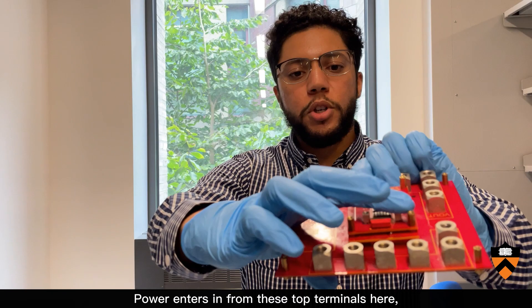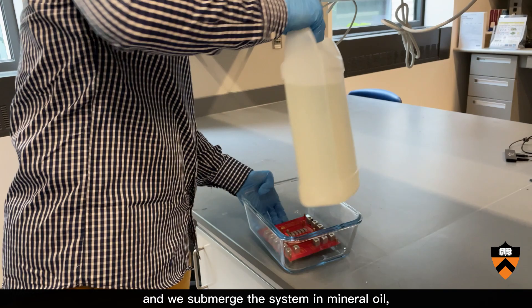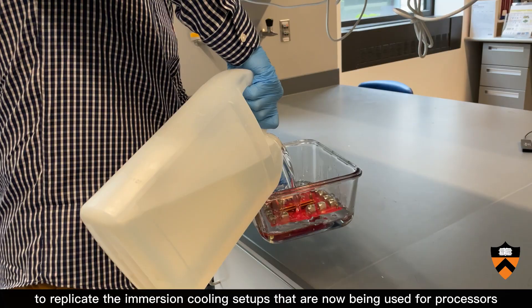So power enters in from these top terminals here, goes through the circuit, and exits from these large terminals and interfaces with the electronic load. We then take this entire system and we place it into a container and we submerge the system in mineral oil to replicate the immersion cooling setups that are now being used for processors that consume a large amount of power.